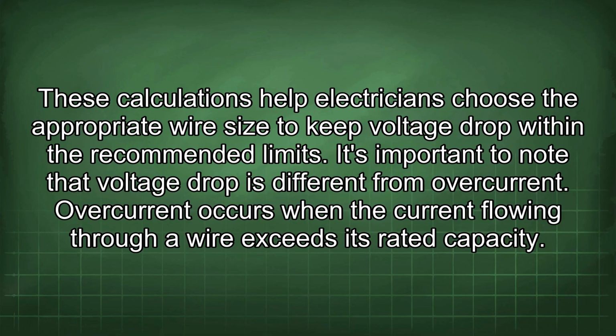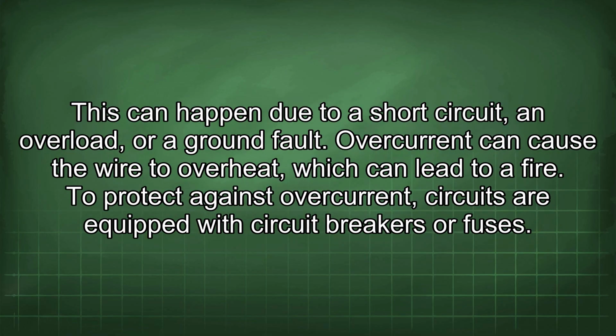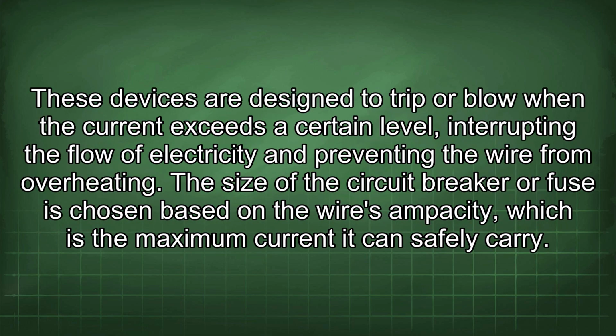It's important to note that voltage drop is different from overcurrent. Overcurrent occurs when the current flowing through a wire exceeds its rated capacity. This can happen due to a short circuit, an overload, or a ground fault. Overcurrent can cause the wire to overheat, which can lead to a fire. To protect against overcurrent, circuits are equipped with circuit breakers or fuses. These devices are designed to trip or blow when the current exceeds a certain level, interrupting the flow of electricity and preventing the wire from overheating.